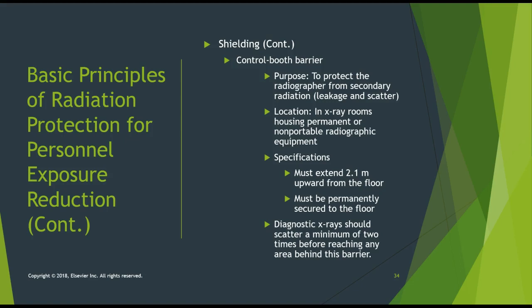Okay, the control booth barrier continued. It's to protect the radiographer from secondary radiation, leakage, and scatter. It is located in X-ray rooms housing permanent or non-portable radiographic equipment, which makes sense. You don't have a control area if you don't have a permanent tube installed. The specifications for the control booth barrier: it must extend 2.1 meters upward from the floor. It must be permanently secured to the floor. That means you cannot have a rolling shield just in front of you in a control area. You must have a permanently designed barrier wall secured to the floor. Diagnostic X-rays should scatter a minimum of 2 times before reaching any area behind this barrier. And you need to know this. This is a test question. Those X-rays should scatter a minimum of 2 times before they ever reach that secondary barrier that you are behind. Okay?